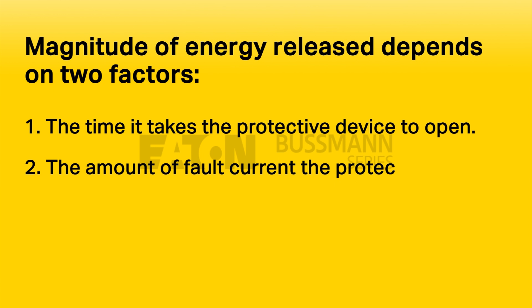Overcurrent protective devices play a significant role in electrical safety. Extensive tests and analysis have shown that the magnitude of energy released during an arcing fault is related to two key factors: the time it takes the protective device to open and the amount of fault current the protective device lets through. The faster the overcurrent protective device clears the fault, the less energy is released. If the protective device also limits the current and reduces the actual fault current that flows through the arc, the lower the energy released. Lower levels of energy released means safer working conditions for the worker and better equipment protection.